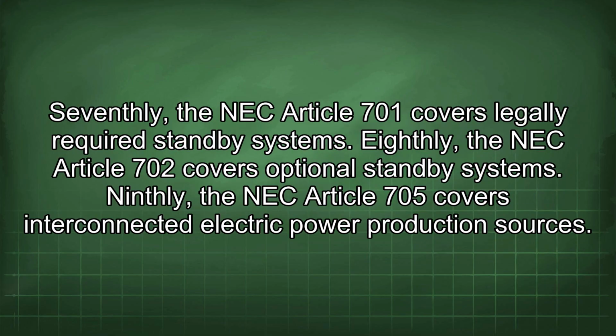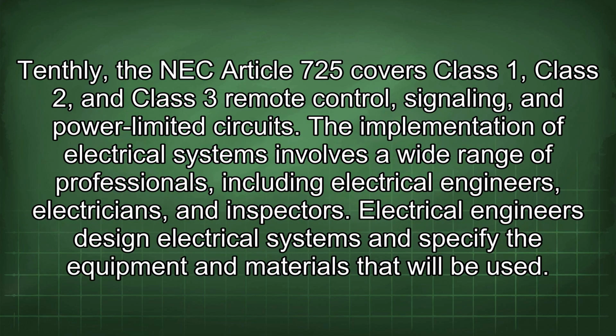NEC Article 701 covers legally required standby systems. NEC Article 702 covers optional standby systems. NEC Article 705 covers interconnected electric power production sources. NEC Article 725 covers Class 1, Class 2, and Class 3 remote control, signaling, and power-limited circuits.